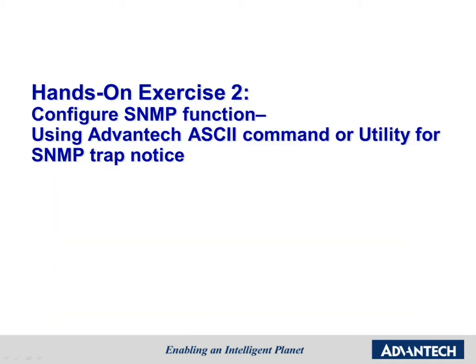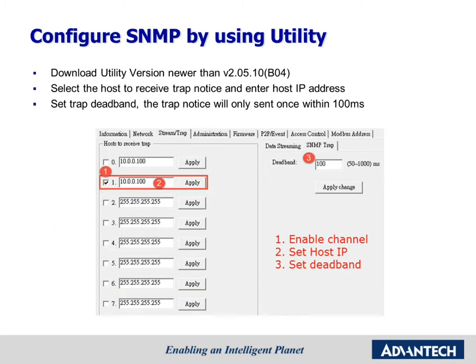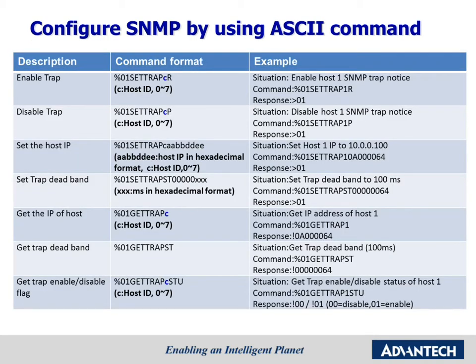Let's move on to the second hands-on exercise: configure the SNMP function using the Advantech ADAM utility for SNMP trap. If the module can send a trap message to the host IP address when an alarm event happens, the maximum number of hosts to receive traps is 8. In the utility version 2.5.10 beta04 or newer, you can set this configuration. First, enable the checkbox. Second, enter the host IP. Last, set the deadband. The deadband determines the minimum interval between triggers of two traps, and it is set to prevent traps from triggering due to noise. These are the ASCII commands for configuring SNMP. We can also use ASCII commands to configure the SNMP function.